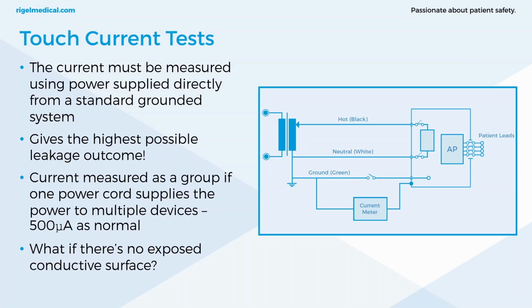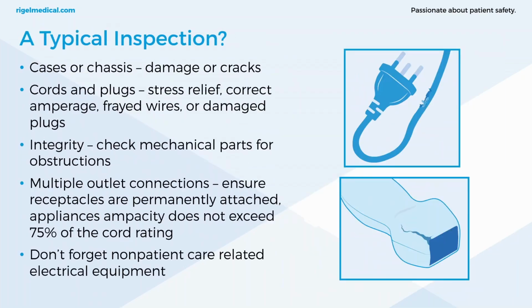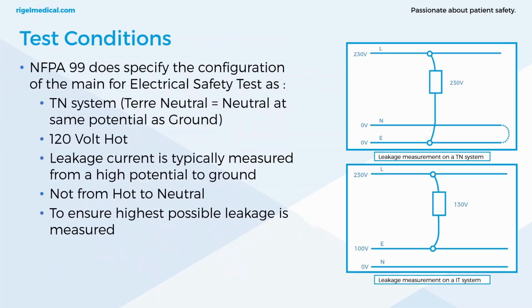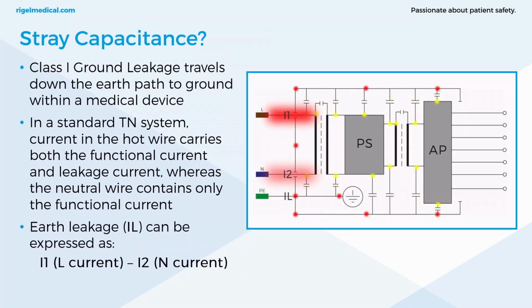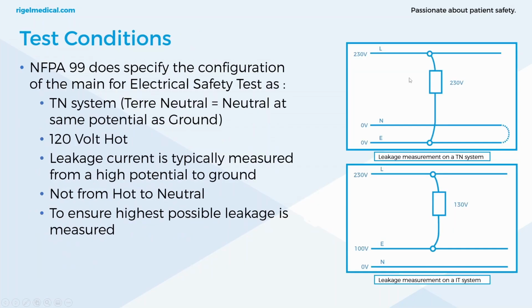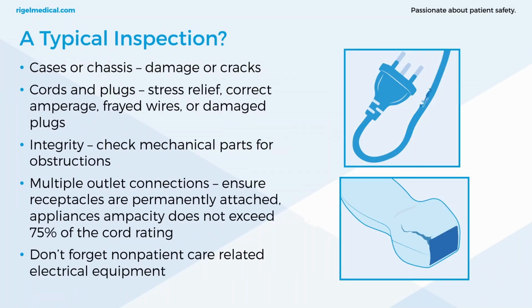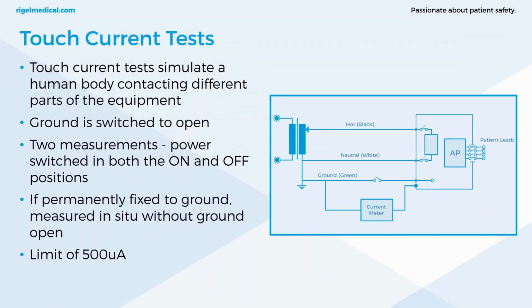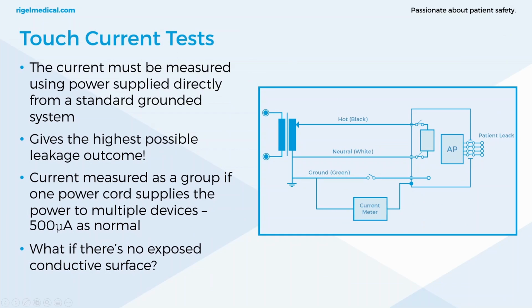Now, if you've got a class 2 device that's fully enclosed, it might seem like a bit of a pointless test, but to go back to one of the first few slides, I have to go back a bit. There it is. If you've got the foil placed on the enclosure, you're still going to have capacitance going to that enclosure, whether it's double insulated or not. And it's a good way to measure any capacitive coupling between the internal components and the enclosure. So it's a useful test for checking the leakages on anything that hasn't got exposed conductive parts.